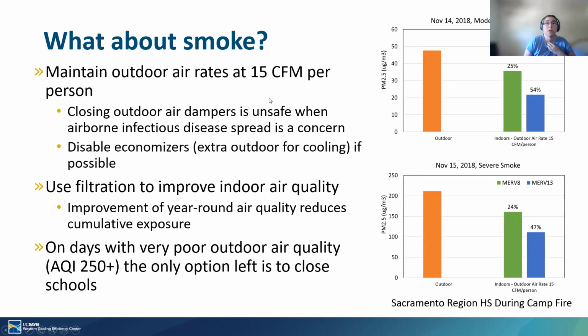And then the question is always, what about smoke? So if we maintain outdoor air rates at 15 CFM per person, one of the questions is, should you just shut off all your outdoor air on a smoke day? And when we're concerned about infectious disease spreading, influenza, COVID-19, we really can't, right? How do we do that? Because we're now increasing this indoor exposure. And so I think the best approach is to keep ventilating at this rate.